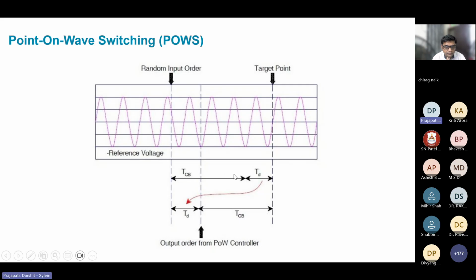So breaker time is defined, and the additional delay for a control target point, which might be a zero of the sine wave or the peak of the sine wave, is achieved by calculating all the operating time factors affecting the closing and opening operations of the circuit breaker. So for example, here, if a random input is given, the device will calculate the additional delay that ensures that the breaker will open at a zero crossing or close at the peak of the wave.